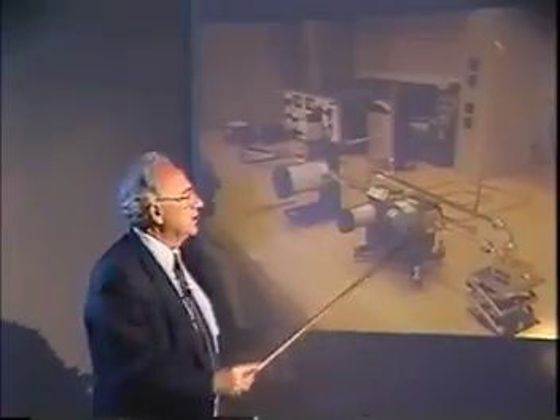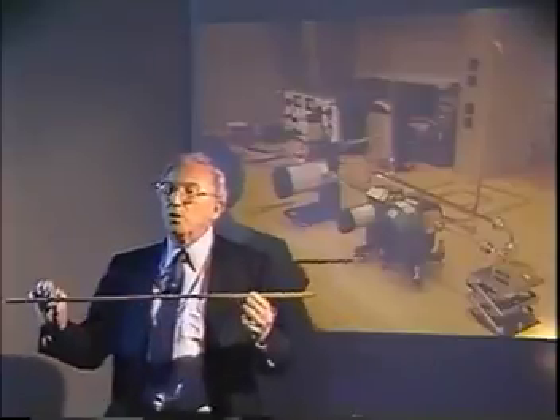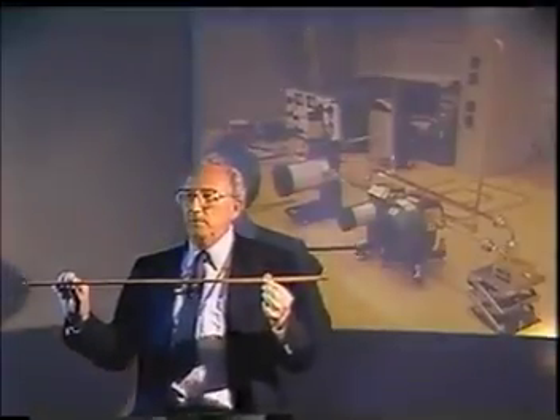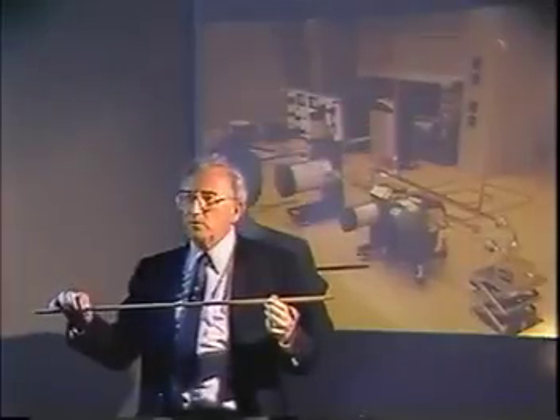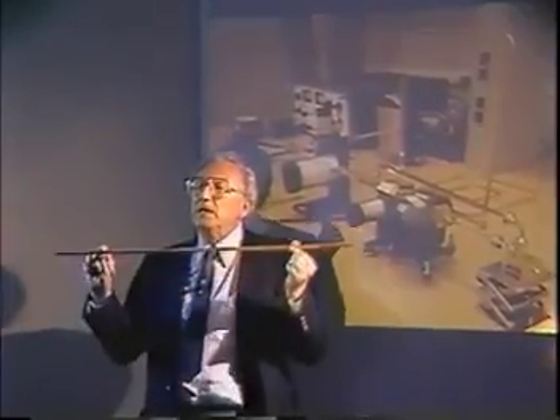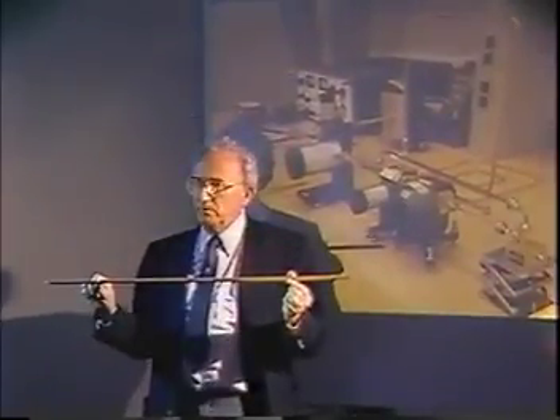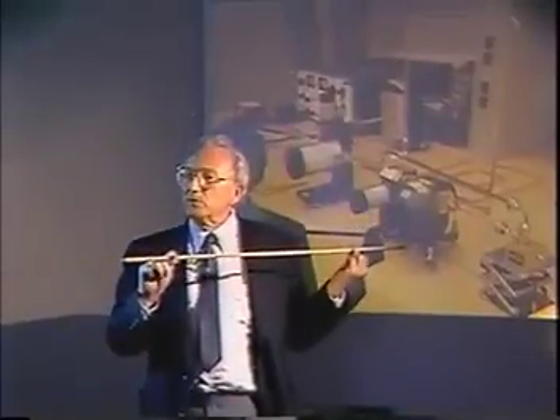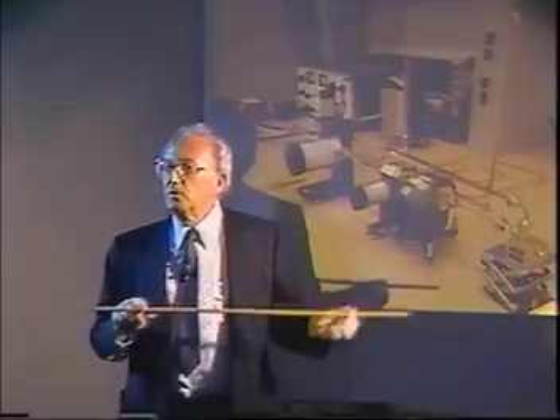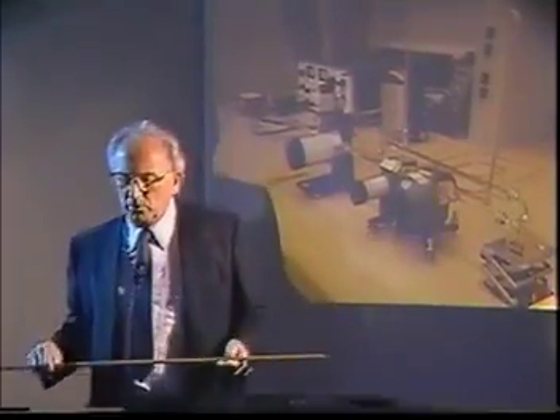Okay. The reason this can be done like this with a waveguide, as you know, you're worried about the delay, the time delay, and the reciprocal of the Fourier frequency gives you the value of time delay. You know that a waveguide is dispersive. However, over this narrow band of frequencies that we're dealing with here, even though it's dispersive, it's not interfering with the actual measurement as far as the decorrelation and the actual calculation of phase noise. But that's what the system looks like for measuring here.